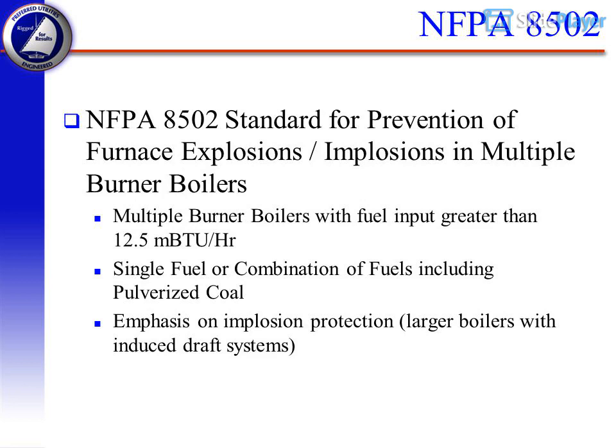NFPA 8502 Standard for Prevention of Furnace Explosions, Implosions in Multiple Burner Boilers. Multiple burner boilers with fuel input greater than 12.5 mBTU/Hr. Single fuel or combination of fuels including pulverized coal. Emphasis on implosion protection, larger boilers with induced draft systems.